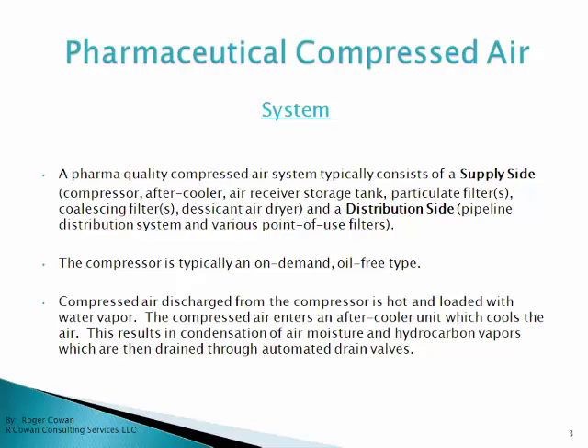Typically, in a pharmaceutical system, the compressor is oil-free and on demand. The compressed air that comes out of the compressor is hot and loaded with water. So the compressed air enters an after cooler unit that cools the air, resulting in condensation of any moisture in the compressed air — and this also includes hydrocarbon vapors. This condensate is then drained through automated drain valves.